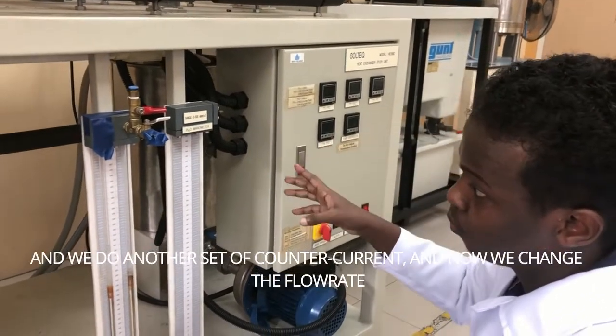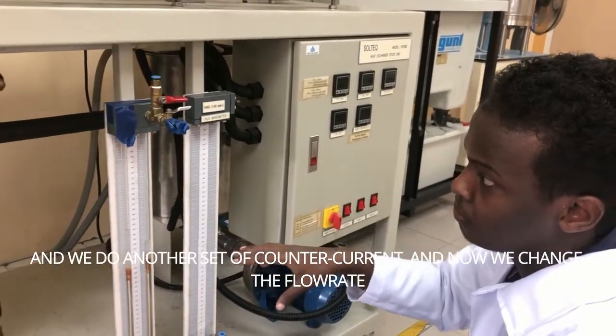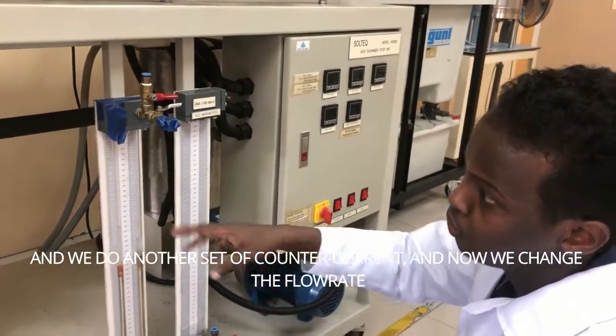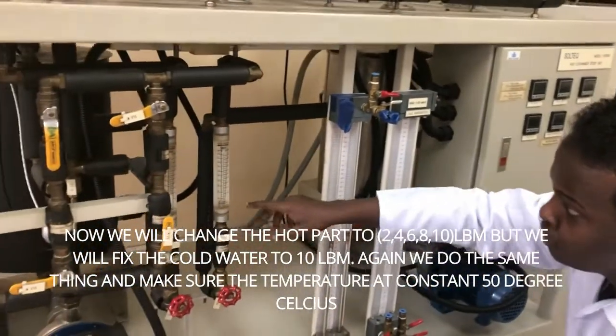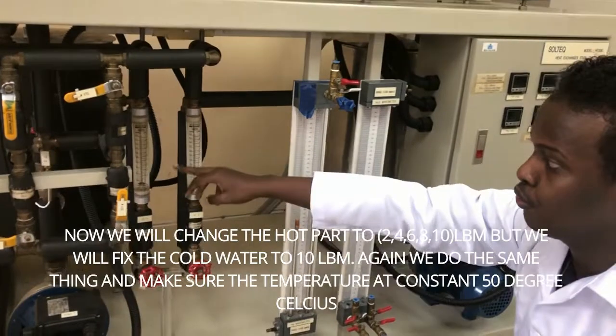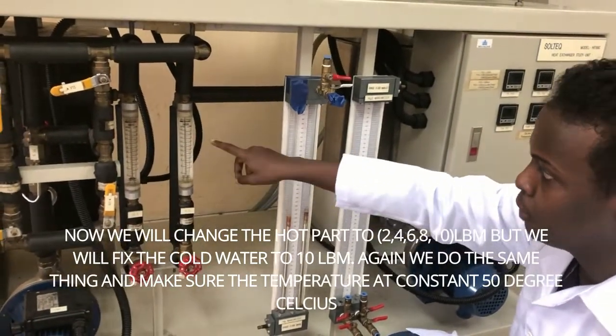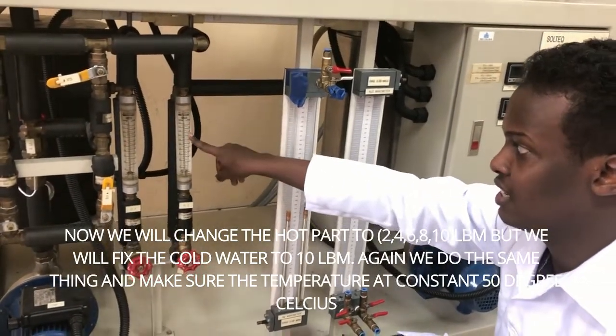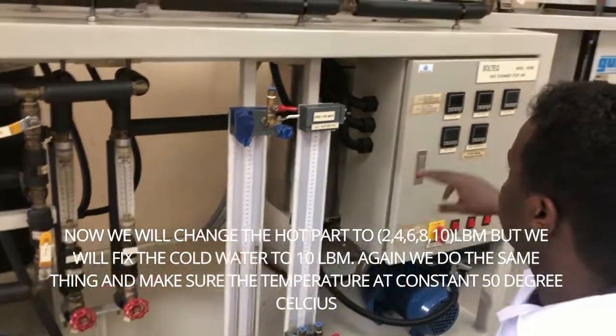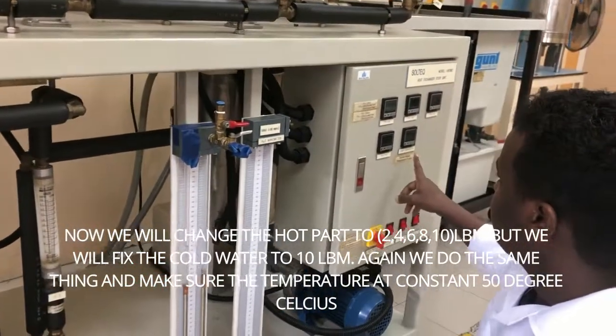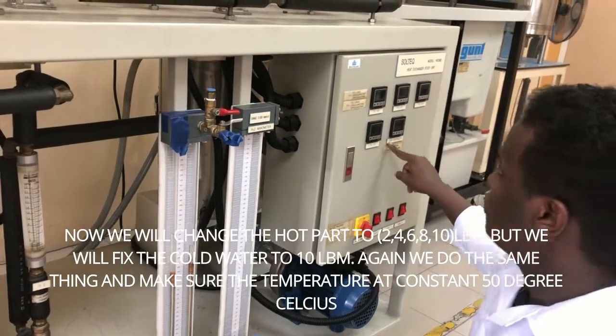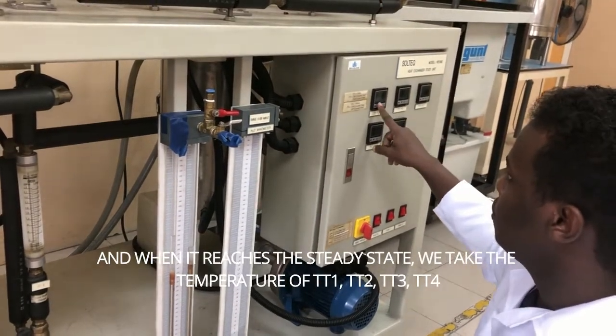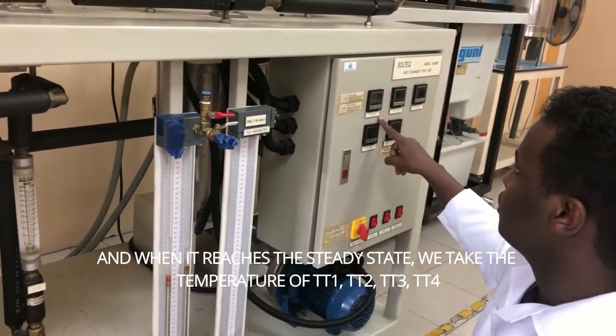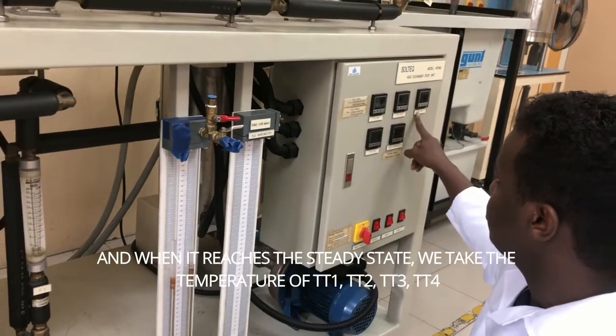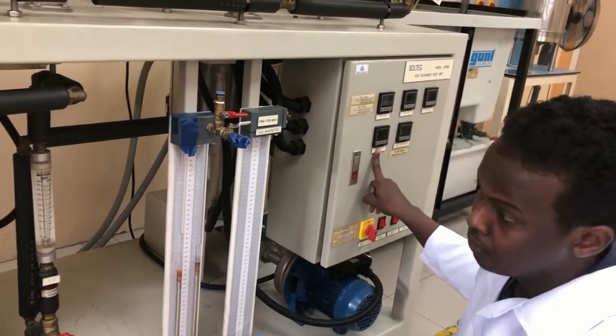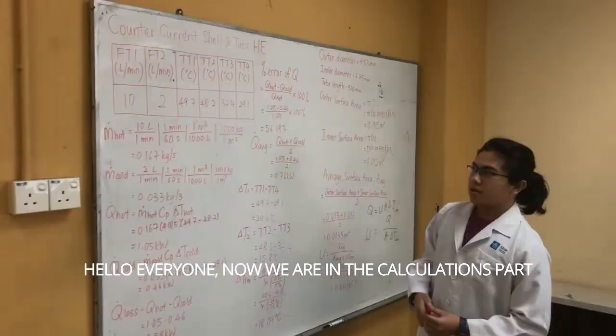And again, we will do another set of the same counter-current. Now we change the flow rate. We will change the hot part to 2, 4, 6 up to 10, but we will fix the cold part at 10 lpm. Again, we will do the same thing. We make sure that the temperature controller is at 50 Celsius. Then when it's at steady state, we take the temperatures T1, T2, T3, T4. That's all.